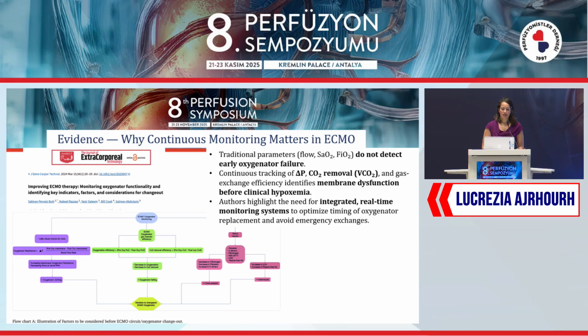This paper suggests adopting an integrated real-time monitoring system that combines hemodynamic and gas exchange data to guide predictive rather than reactive management, allowing teams to plan oxygenator replacement in advance, avoid emergency changeouts, and improve both safety and cost effectiveness.